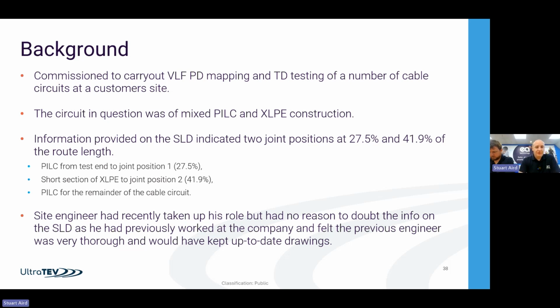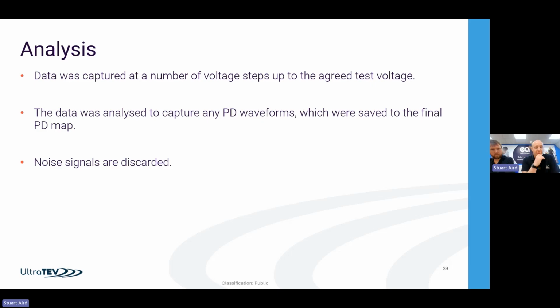So I'll just explain a little bit what we do. We're going to energize the cable. The difference with offline testing as well is you can raise the voltage slowly, so you're not going to go from 0 to full voltage, and you have the advantage of also going above operating voltage. So you can do things like tan delta at the same time, and you can stress the cable a little bit more and pick up any PD, up to generally 1.5 times operating voltage these days.